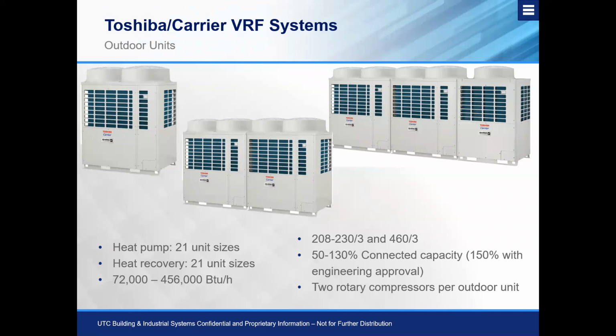These are available in a 208, 230 three-phase and 460-volt three-phase application, and these will range from a 50% minimum to a 130% maximum connected capacity ratio, with the ability, with factory support and engineering approval based on the application, to get up to 150%, to make sure that we're not going to dig a hole for ourselves and apply more indoor unit capacity than we actually have for the outdoor unit.